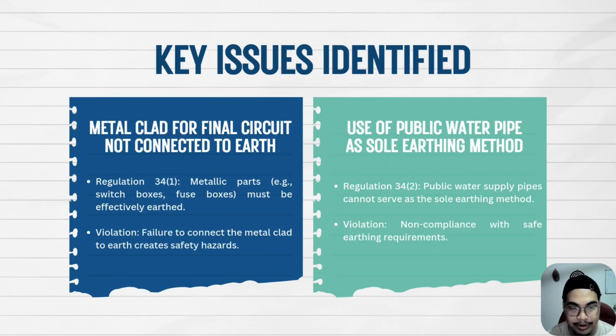After carefully studying the question, we find two key issues. The first is the metal clad for the final circuit not connected to earth. Based on Regulation 34(1), metallic parts, for example switching box or fuse box, must be effectively earthed. In this case, failing to connect the metal clad to earth creates a safety hazard.